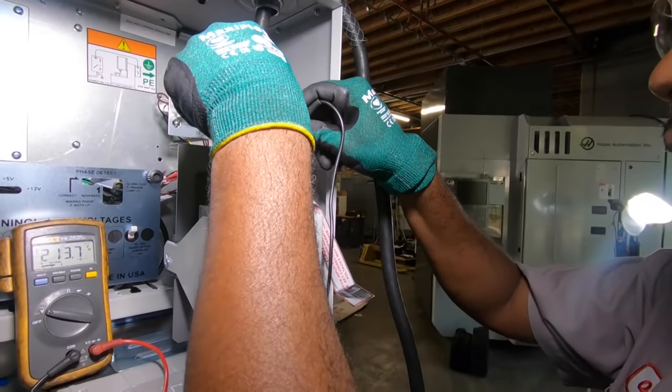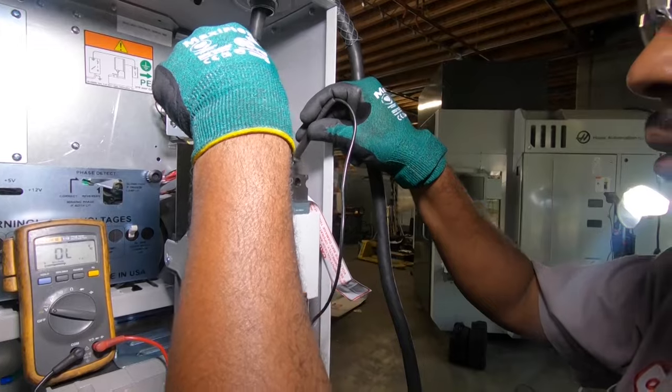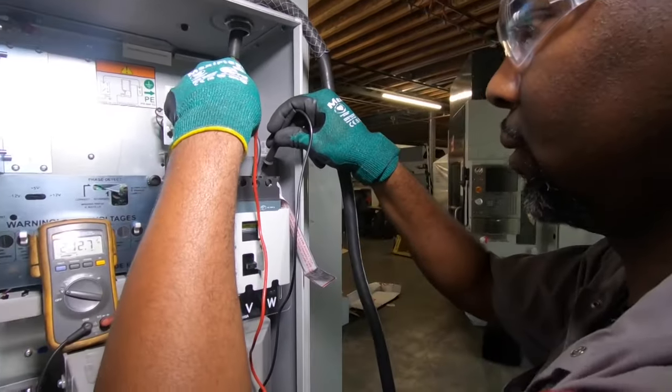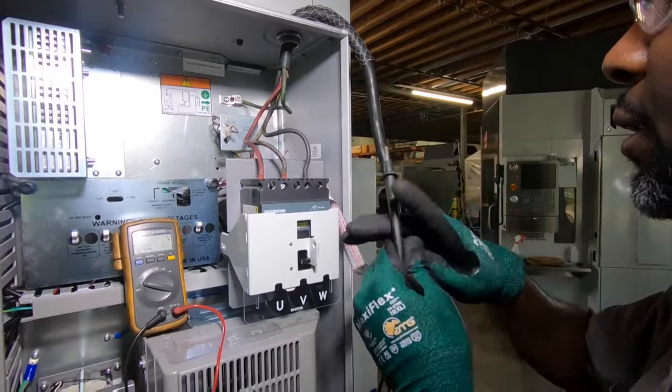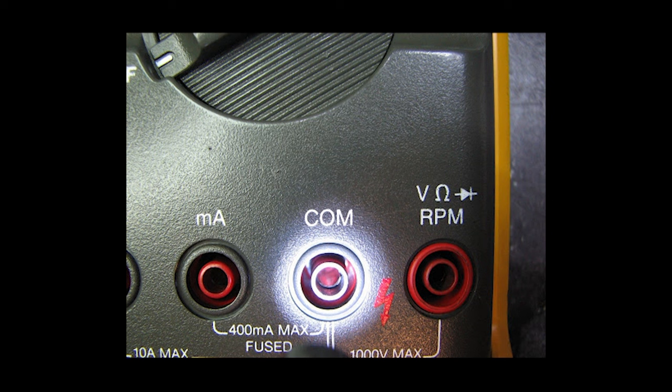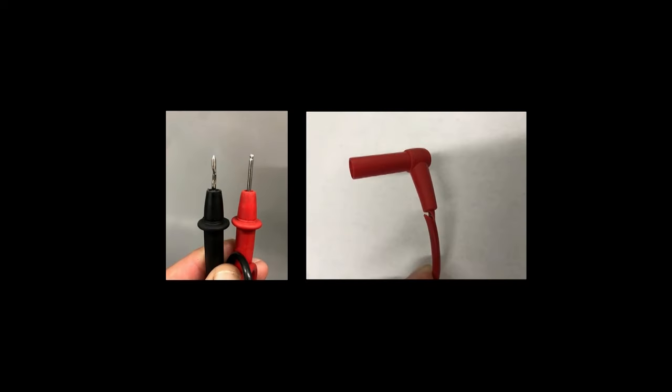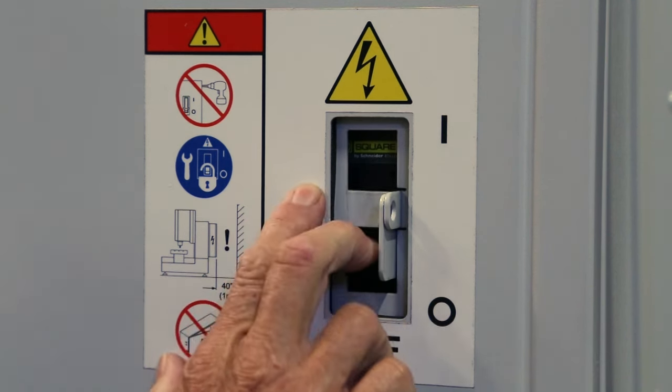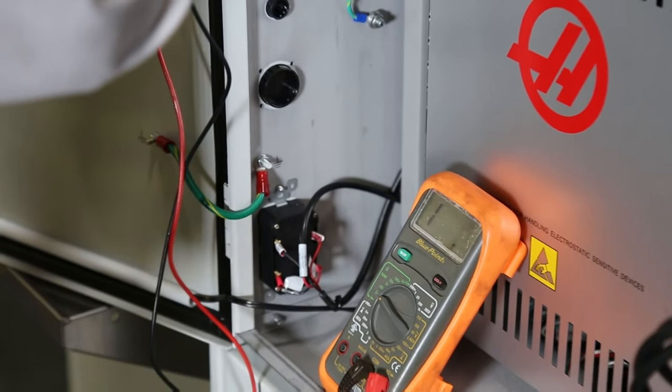Now when you use a multimeter, you may be touching electrical connectors in an energized circuit, some with many amps of current and very few ohms of resistance. Here's what you can do to be safe. First, inspect a multimeter case for cracks or signs of damage. If you find anything that seems a little odd, use a different multimeter. Do the same thing for the probes. Never use a probe if it's damaged in the slightest. If possible, de-energize the circuit before you test it.